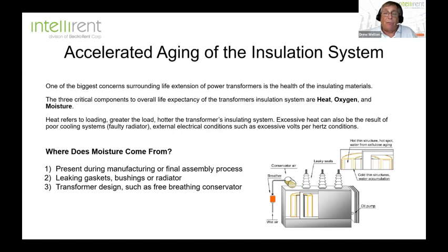Transformer designs such as free breathing conservator, and we see this down here. If we look at the desiccant right here, if the desiccant isn't working properly and we don't have a good nitrogen blanket, water from the atmosphere can become an issue.